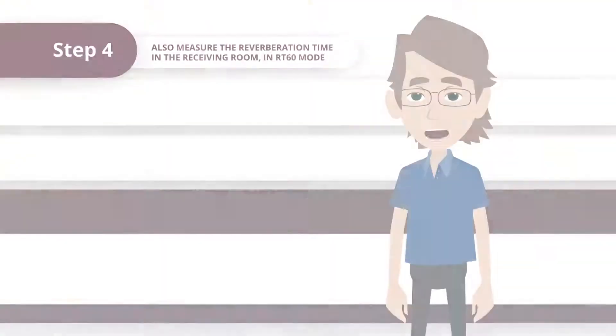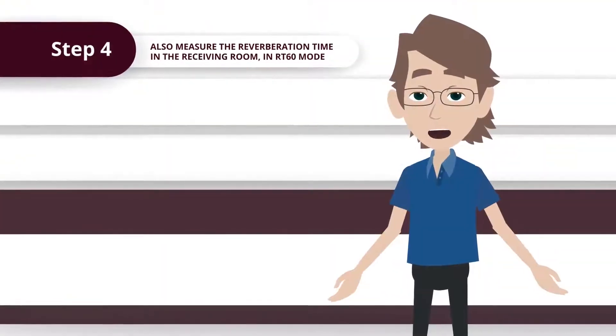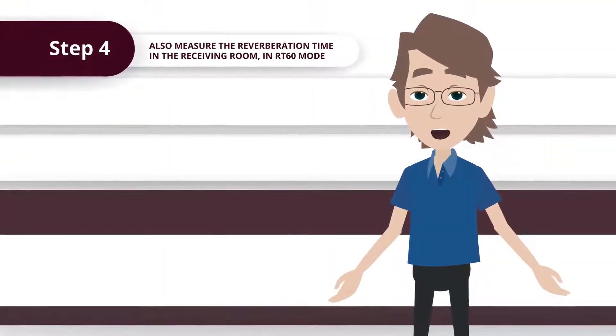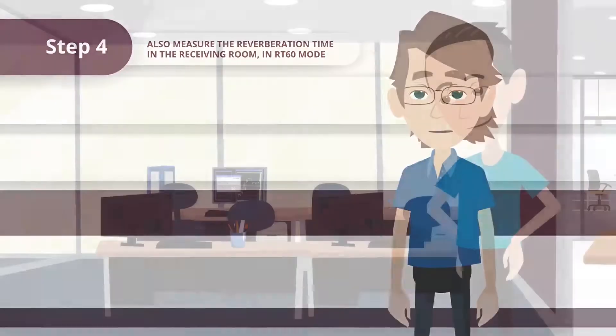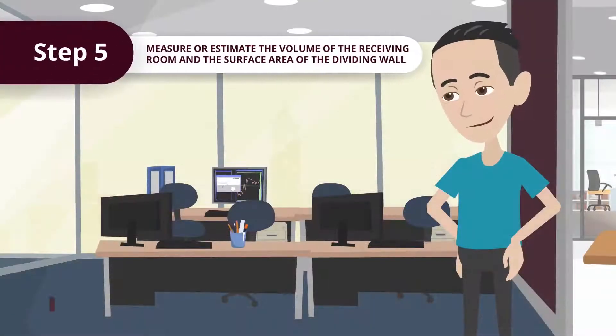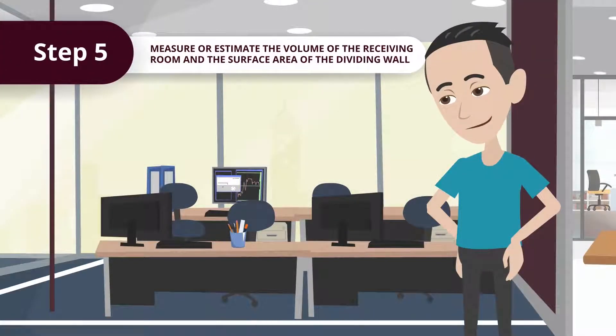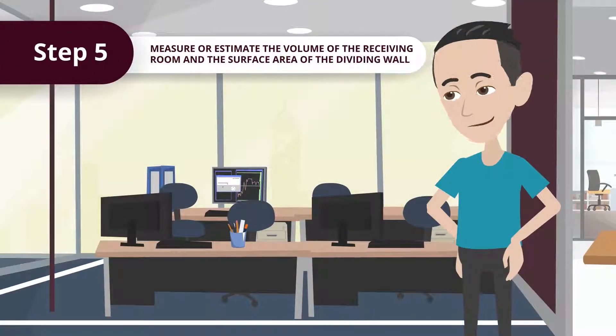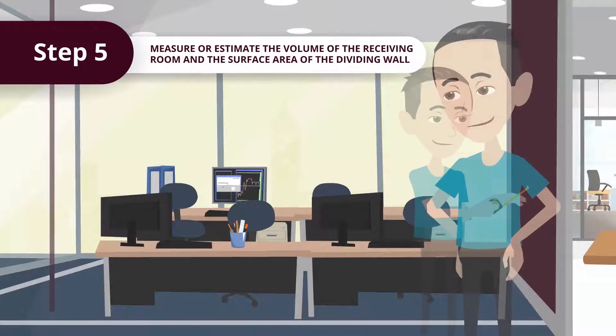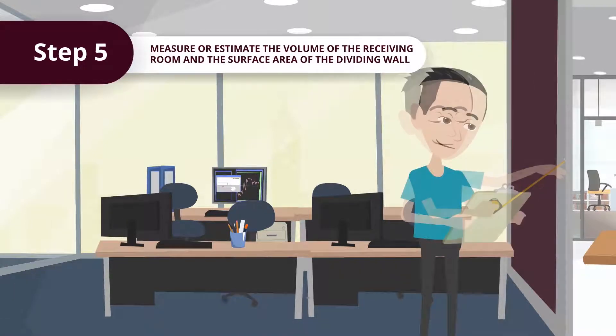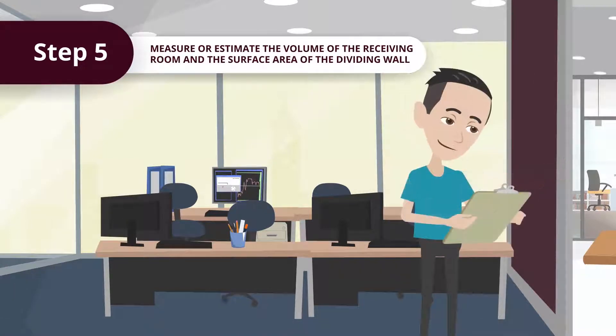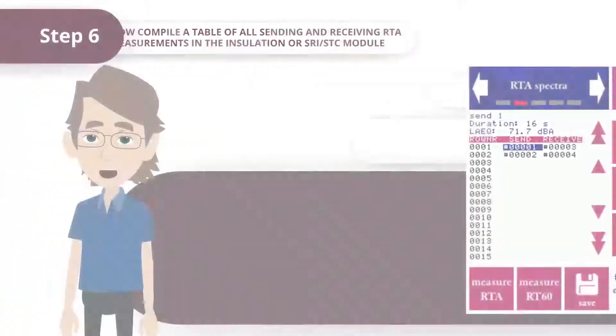Step 4: Also measure the reverberation time in the receiving room in RT60 mode. This is needed for corrections applied during the calculation of insulation values. Step 5: Measure or estimate the volume of the receiving room and the surface area of the dividing wall. These are also needed for corrections.